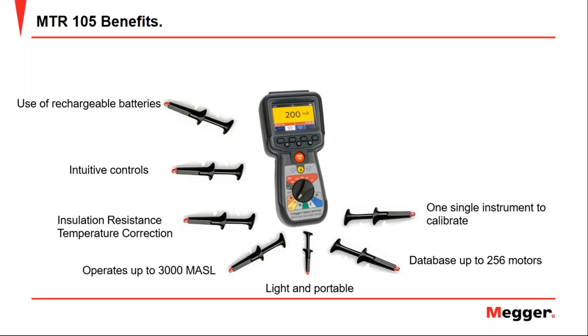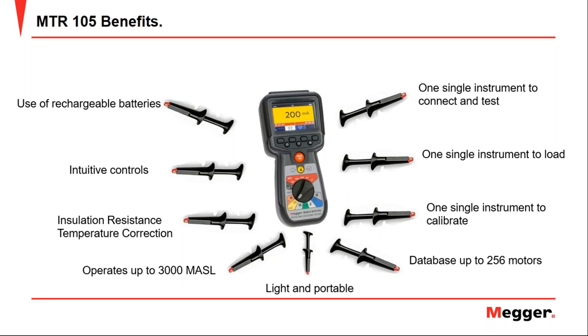And this is maybe the most important thing. You're going to have only one single instrument to calibrate. You don't have to send 4, 5, 7, whatever number of equipment you have, to calibrate. You just have to calibrate one and only one equipment. One single instrument to load, and because it's very light, it's a great benefit. And of course, one single instrument to connect and test in the motor. So at the end of the day, we have seven equipment in just one. All these tests that we are talking about in this webinar, the MTR-105 can do.